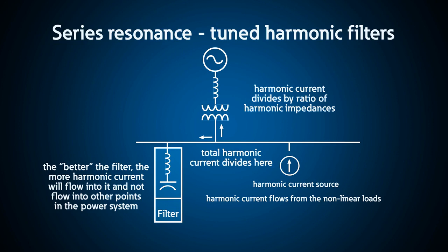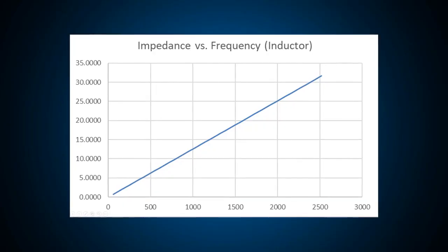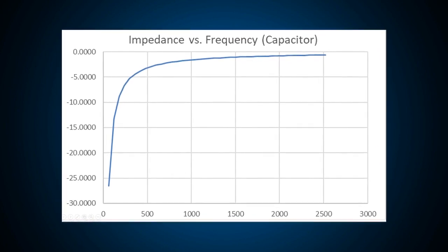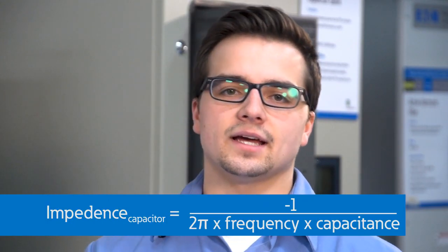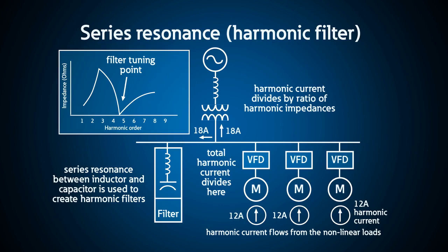Let's back up a second and define resonance. Series resonance occurs when you put a capacitor in series with an inductor — we call this a harmonic filter. We tune this filter to a specific frequency by selecting the components that match impedance at the desired tuning frequency. Since the impedance of an inductor is defined by 2π times frequency times the inductance, its impedance increases as the frequency increases. The impedance of a capacitor is the opposite — it decreases as the frequency increases because its impedance is 1 over 2π times the frequency times the capacitance. When the two impedances match, the filter is a very low impedance, almost a short circuit, aside from a little bit of resistance. Harmonic current of that frequency will want to go through that filter path, dividing to the path of least impedance, so the closer you tune a filter to the frequency you want, the more effective it is.